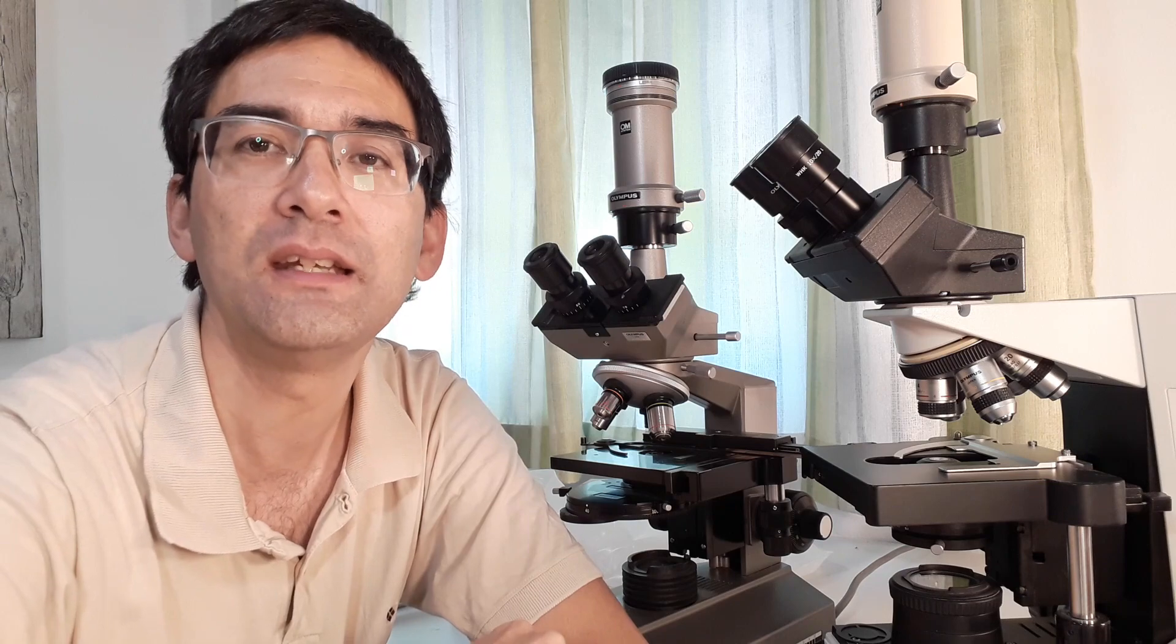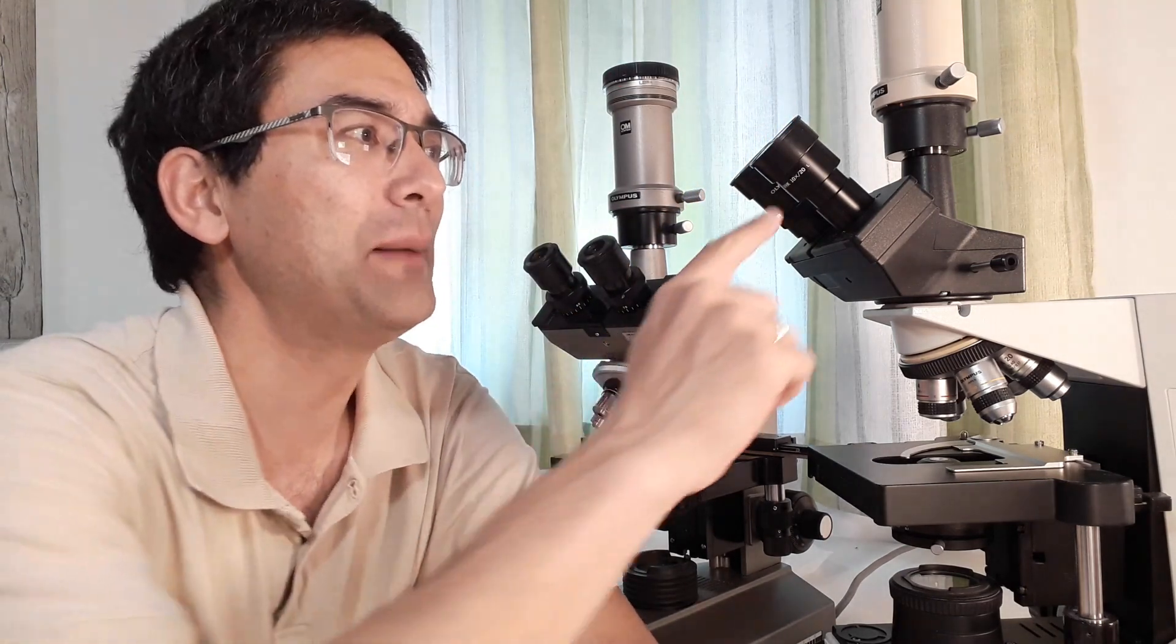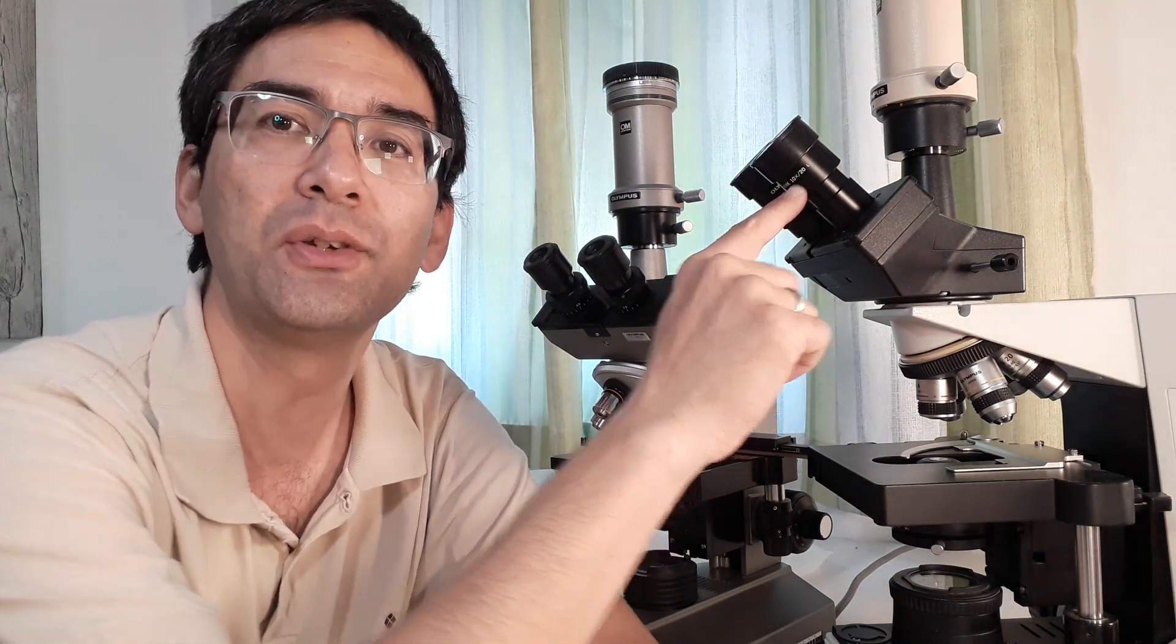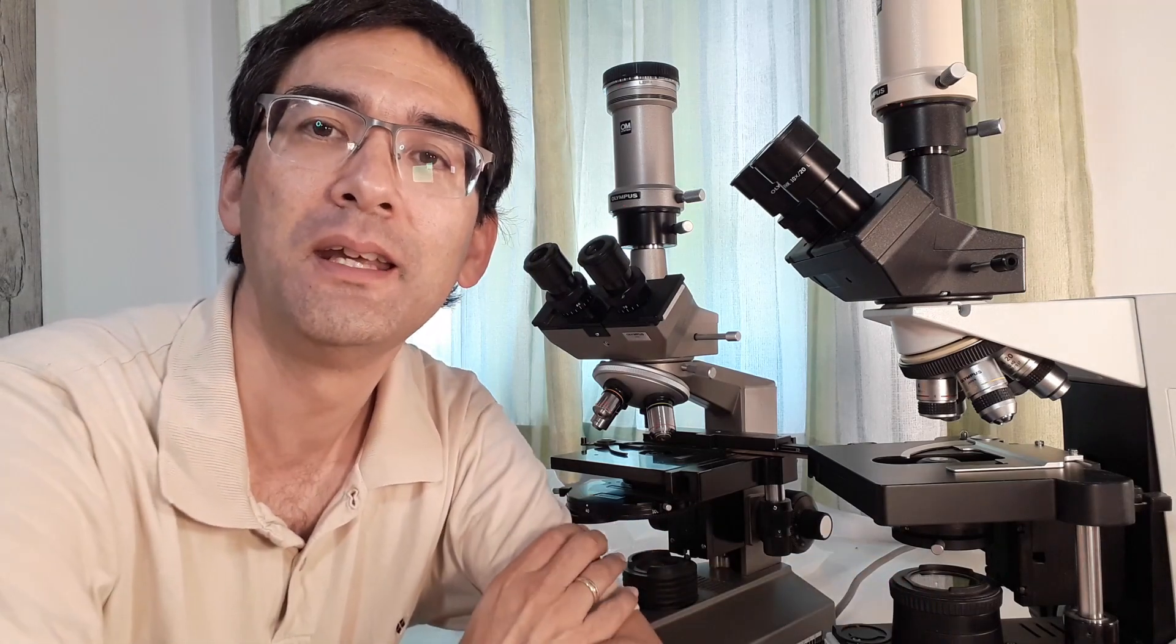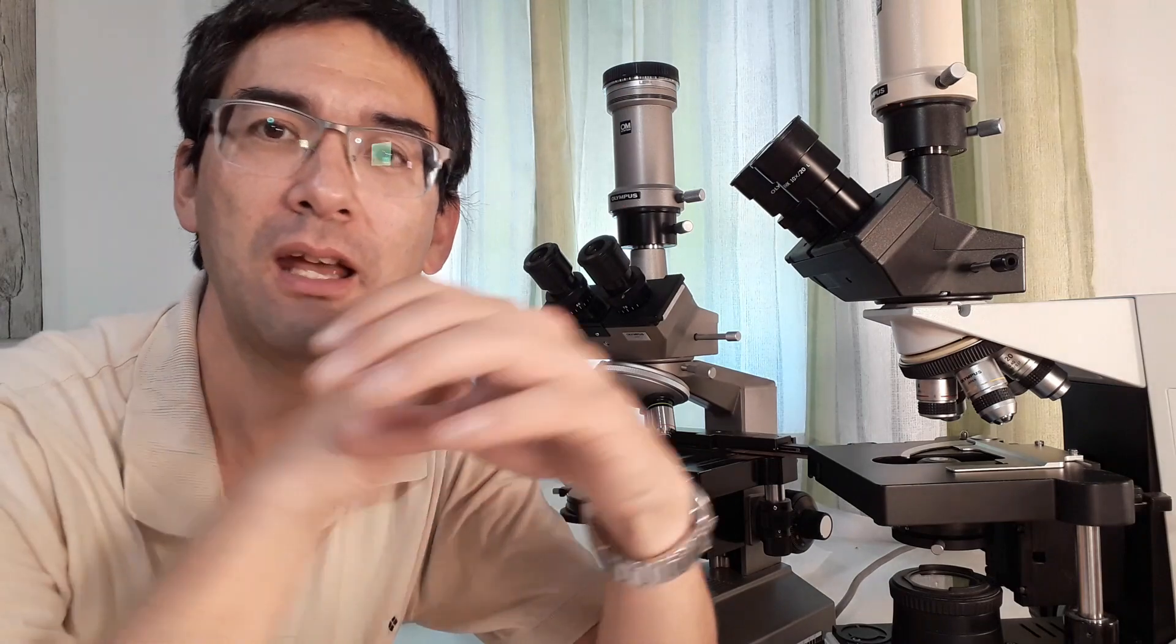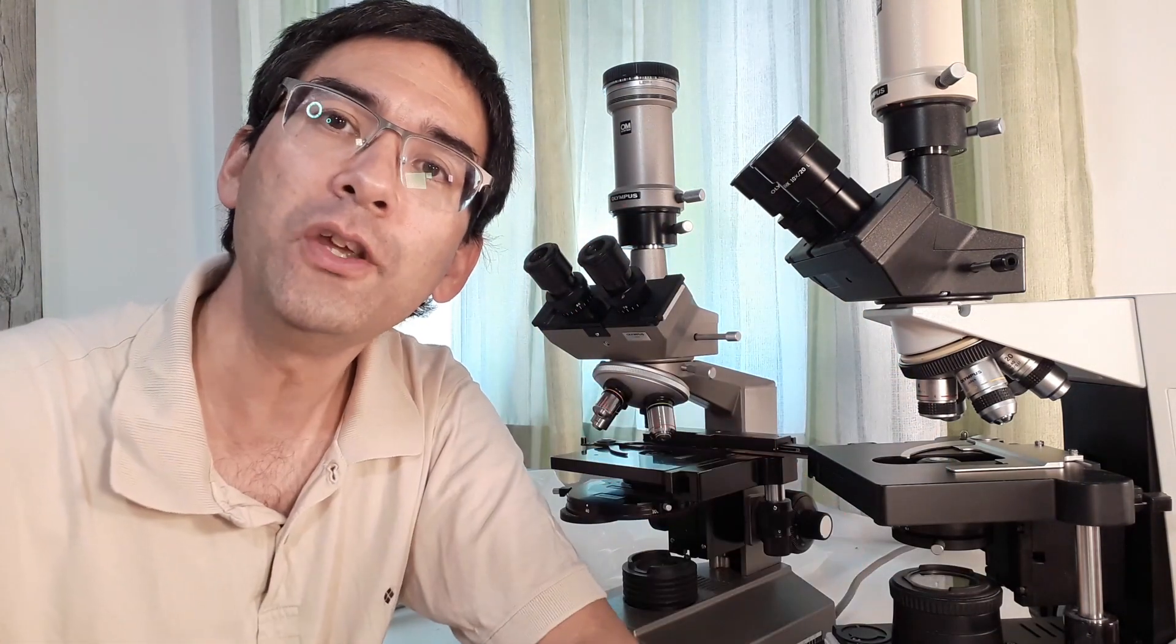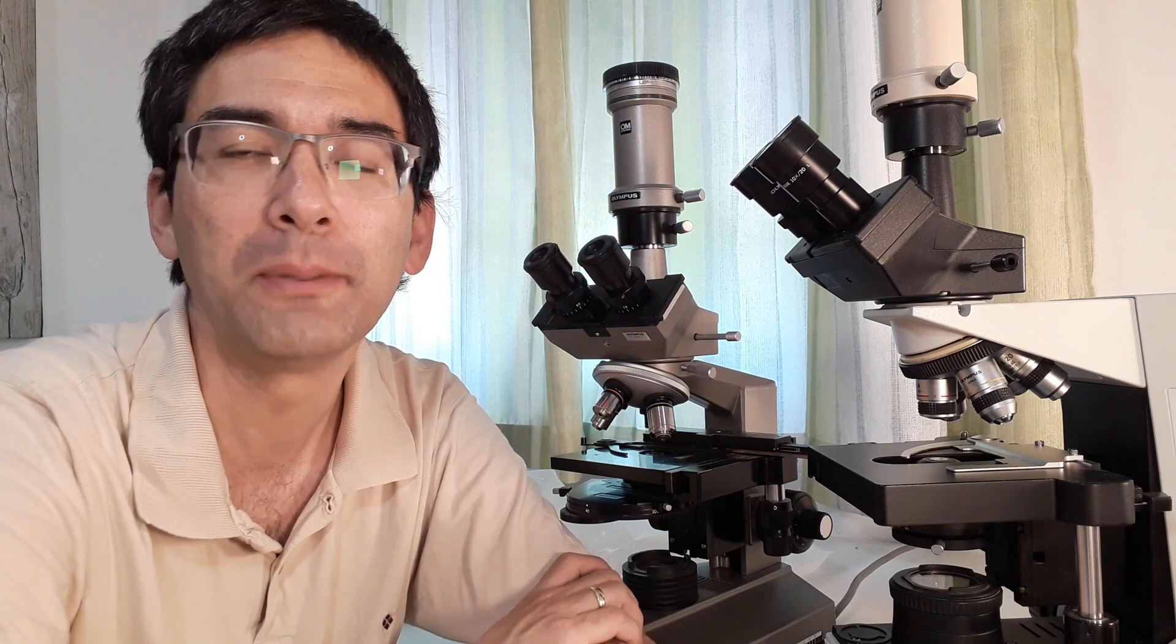But if you're interested in taking photographs, especially through the eyepiece, for example this eyepiece here is a wide field eyepiece with field number 20, which means you can see quite a bit more of the specimen compared to eyepieces with a smaller field number. If you want a wide field of view, then you want to also exchange the eyepieces to get the benefits of the plan objectives.